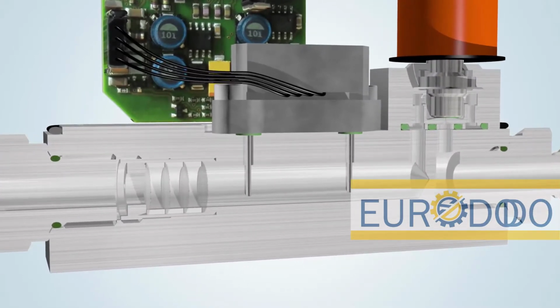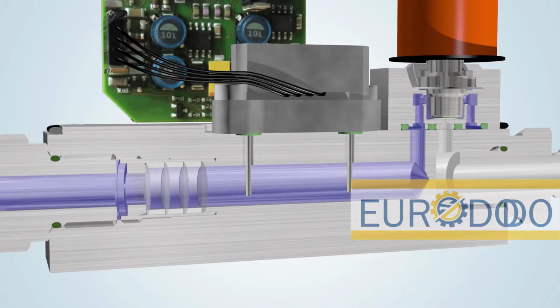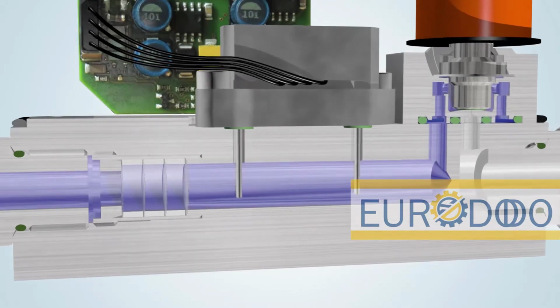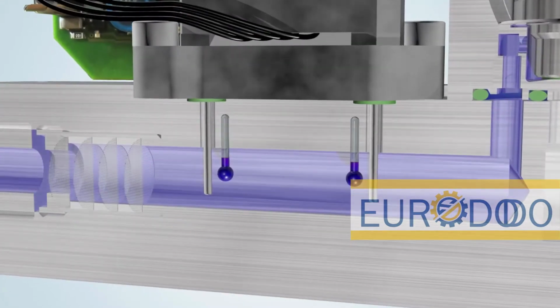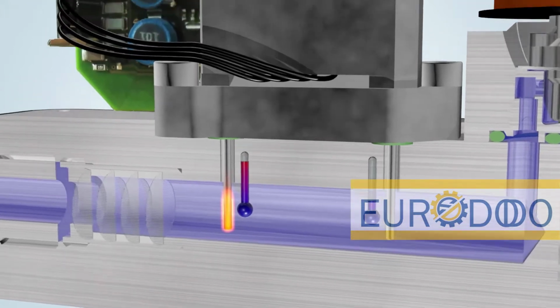Once the instrument has been connected to the process line, the pre-pressure can be set. The body is now filled with gas. The flow sensor consists of two stainless steel pins encasing the heater in the first probe and the temperature sensor in the second probe. A constant temperature difference, or delta T, is created between the two sensor probes. Since the control valve is still in the closed position, the measured value corresponds with zero flow.